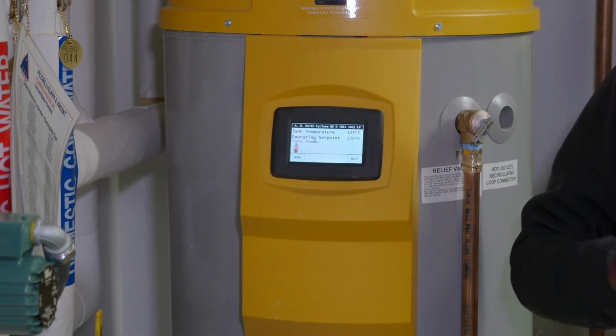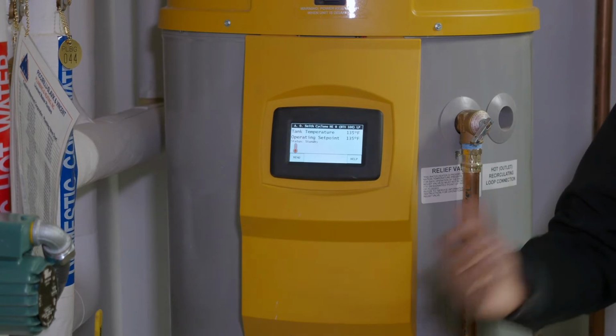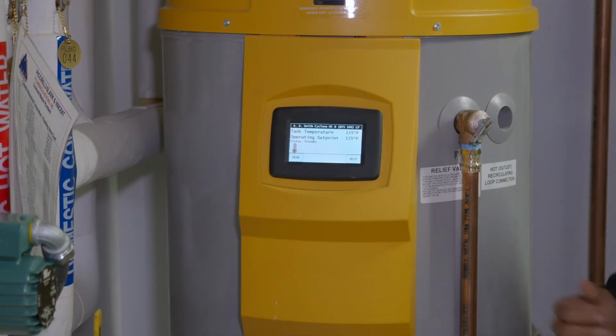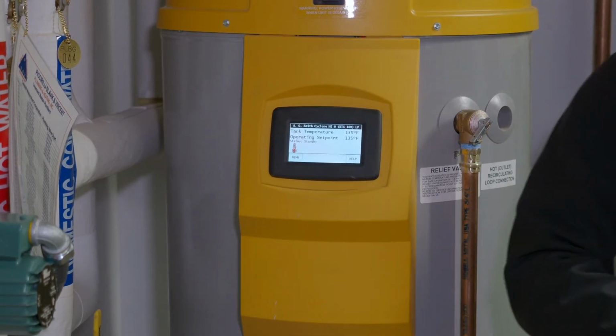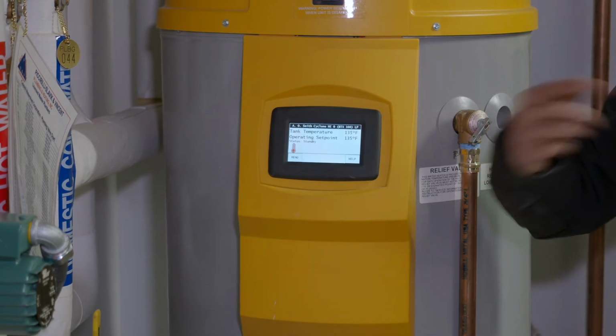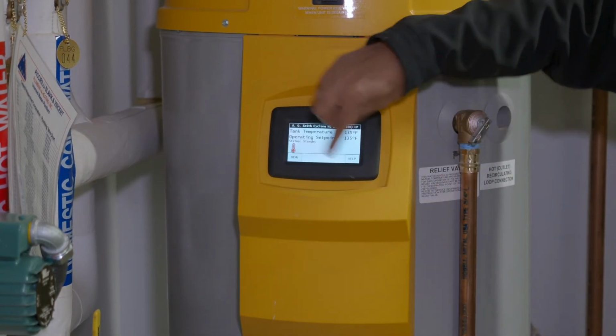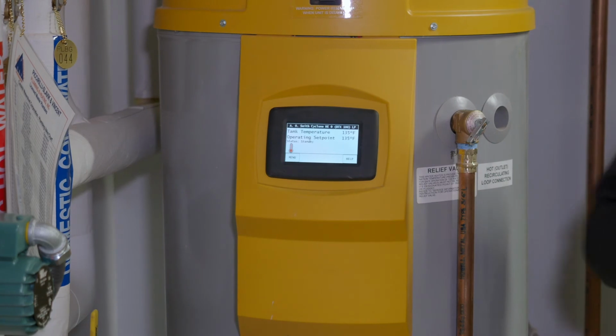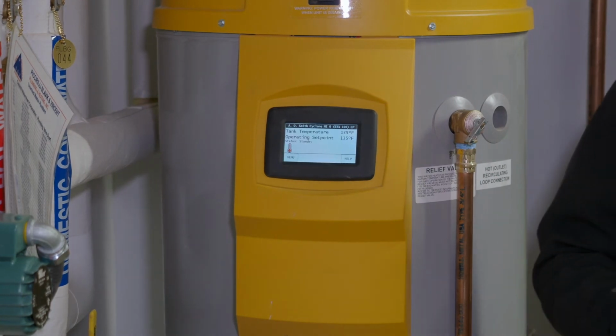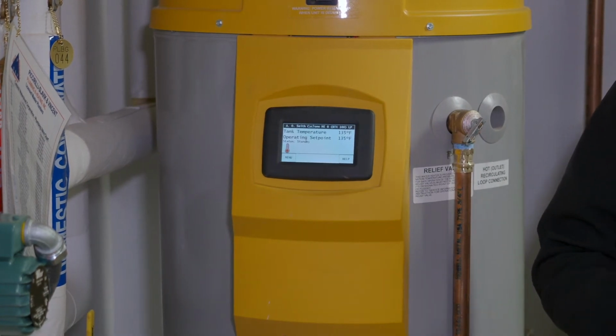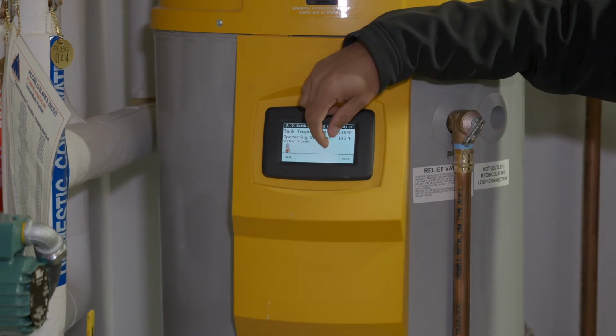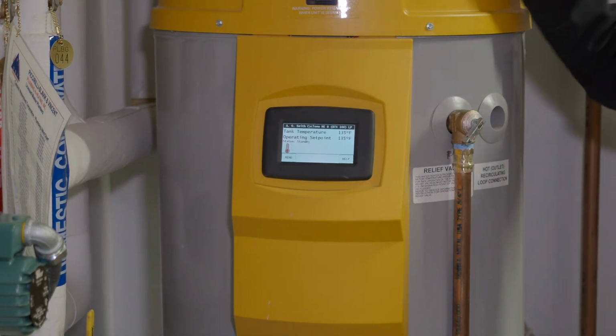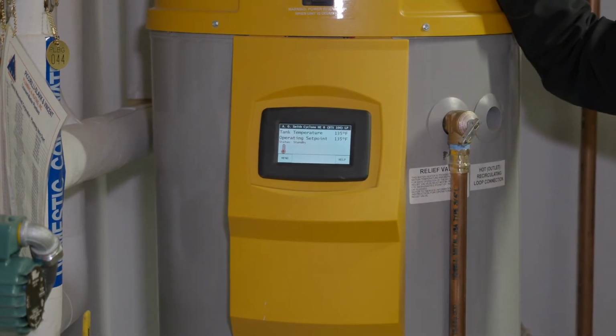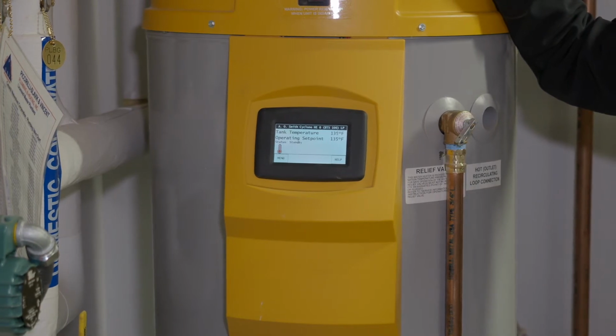That means when there's a call for hot water and the faucets are on, you're going to do a pre-purge cycle. The blower's going to kick on, and you're going to see a little fan spinning around symbol. And then once everything's free and clear, it proves that we're good to fire. You're going to see a flame signal there, and that's going to run until the tank is satisfied to whatever predetermined temperature it's set at.